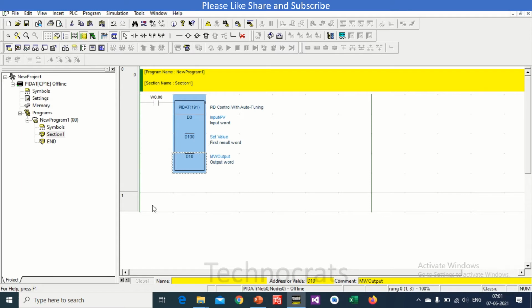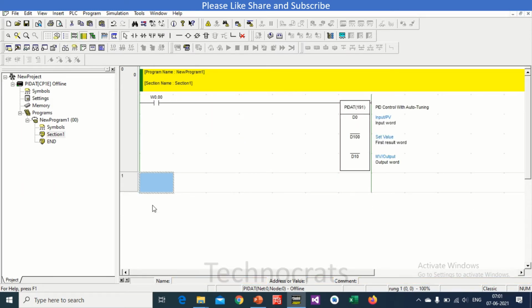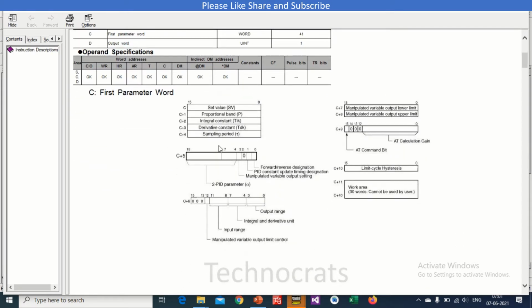Okay, now moving towards the parameter section, that starts from D100 and goes further. Let me show you the instruction help. So the first parameter is set value, the next is proportional band, then integral constant, then derivative constant, then sampling period, then forward/reverse designation, PID constant update timing designation, and C6 is your manipulated variable output limit control, input range and unit output range, then C7 is your manipulated value output lower limit and upper limit, that is C8.